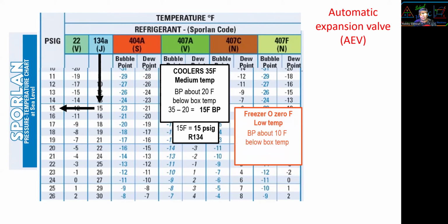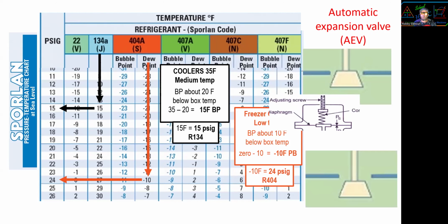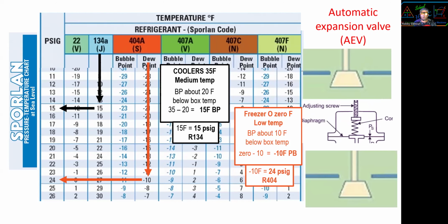Freezer 0 degree low temp. Boiling point about 10 degrees below box temperature. 0 minus 10 equals negative 10 boiling point. Saturation temperature, whatever you want to call it. Okay, so negative 10 equals 24 psig. I set my pressure control at 24 psig. I don't have to worry about it. Okay, and you adjust it up and down as pressure.